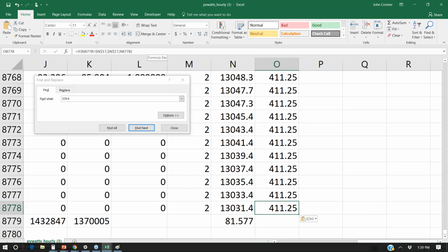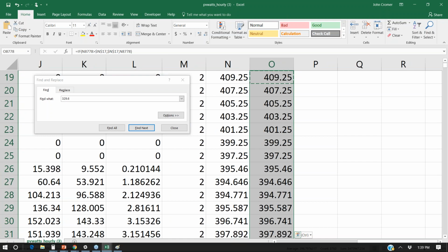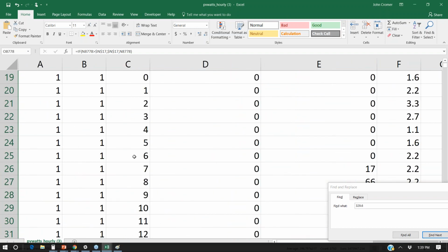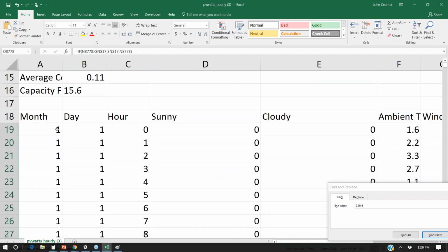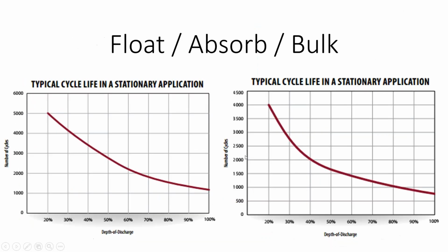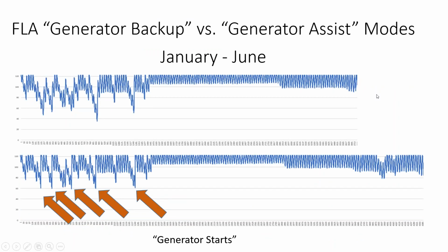And then you could even chart your total battery bank size and your other axis of the hours of the day and days of the year. You'd have to convert this into a little bit better granular data, but I'll show you the end result. As we went and charted our 122 kilowatt hour battery bank for every hour of the day, every day of the year, we can actually see the weather systems roll through.